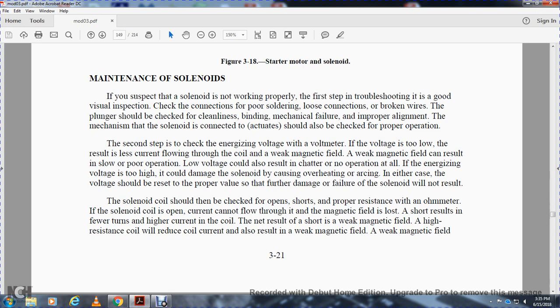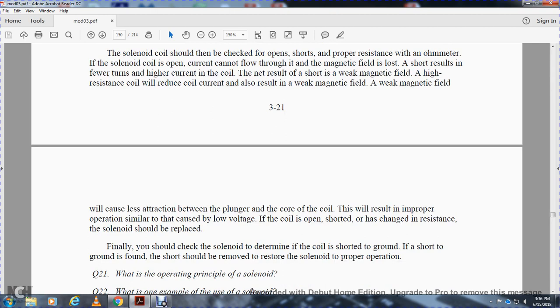The solenoid coil should then be checked for open or short with the proper resistance reading on an ohmmeter. If the solenoid coil is open, current cannot flow and there is no magnetic field. A short results in reading a lower resistance, with a few turns shorted, higher coil current. The net result is a shorted, weaker magnetic field. Higher resistance will reduce the coil current, resulting in a weak magnetic field. The weak magnetic field will cause less attraction between the plunger and the core of the coil, resulting in improper operation. If the coil is open, shorted, or has the wrong resistance, the coil should be replaced.